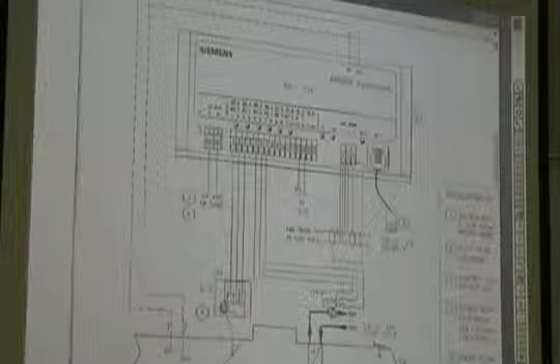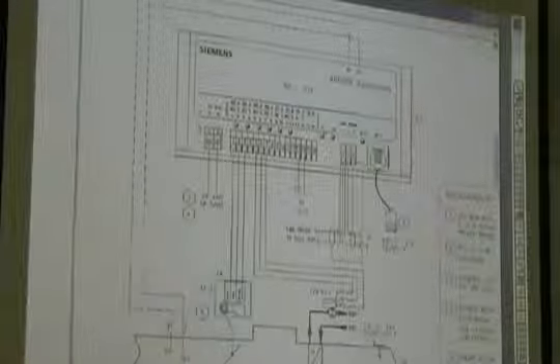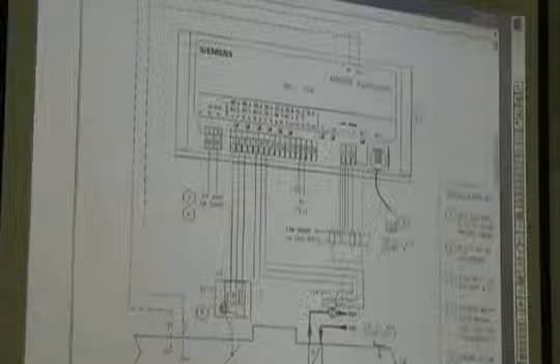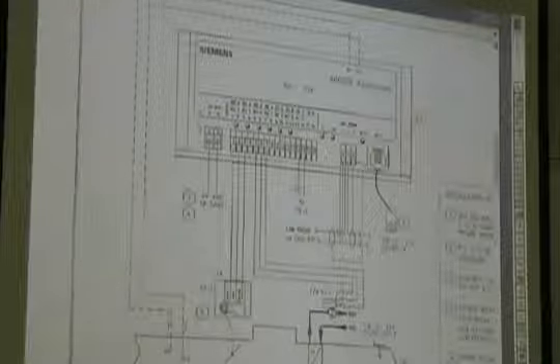So if I turn that one DO on, the one that makes it open, for 10 seconds, I've driven that motor 1/9 of the way open, I guess. Okay, if I turn the other DO on for 10 seconds, it closes right back. And that thing is precise enough that it knows that if I've been on for a second and a half, I've moved so far. And on a 90-second motor, you basically have 1 second per degree. And so if I want to go to 45 degrees, I run it for 45 seconds. If I want to move back the other direction 10 degrees, I turn the other DO on for 10 seconds.